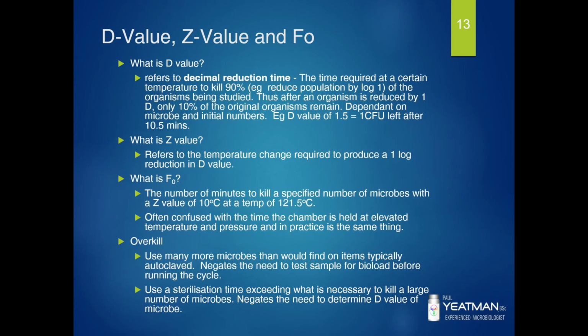Ideally, you would determine the D value yourself, but to do that you need what's known as a BIER vessel, which is a biological indicator evaluation resistometer. And last thing I checked, this costs about 100,000 US for one of them, which can be outside the budget for most organisations. A spore supplier D value along with robust validation is vital to demonstrate your autoclave's effectiveness.